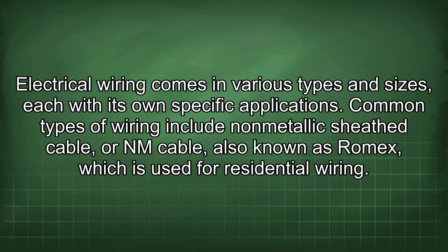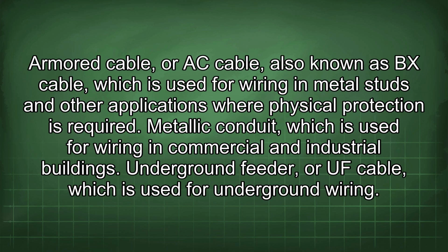Electrical wiring comes in various types and sizes, each with its own specific applications. Common types of wiring include non-metallic sheath cable or NM cable, also known as Romex, which is used for residential wiring. Armored cable or AC cable, also known as BX cable, which is used for wiring in metal studs and other applications where physical protection is required.